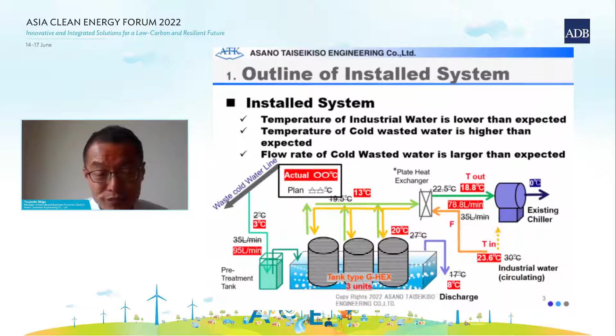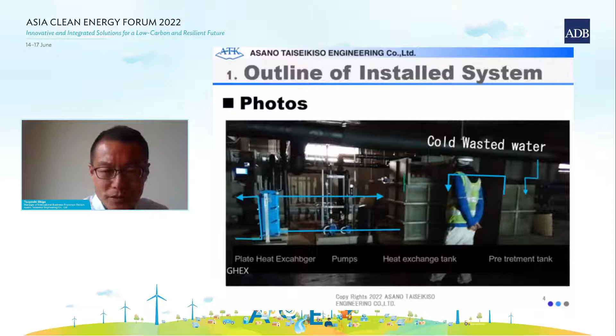The cold wasted water comes into the treatment tank from the wasted water pipeline, and the water goes into the main heat exchange tank. The circulated water inside the GHEX is cooled down, then the cooled water goes into the plate heat exchanger, where the industrial water is cooled down. That is the principle of the system.